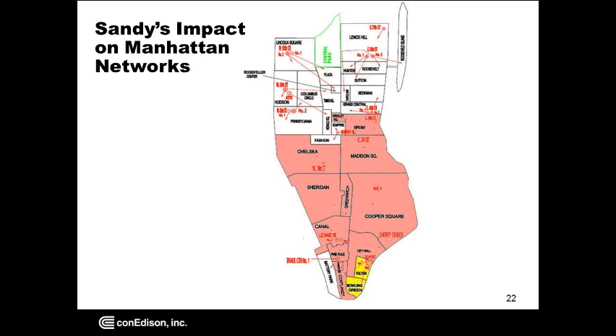The networks in red lost power because of a flooding situation at our East 13th Street substation, where relay cabinets were flooded. Even though we have flood protection at that substation, the protection goes to 12 feet. We had about 14 feet, so it overwhelmed the flood barriers.